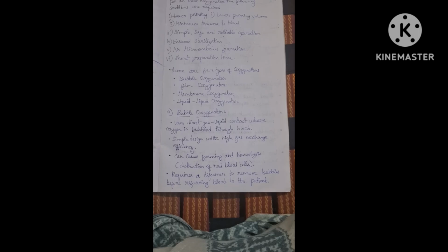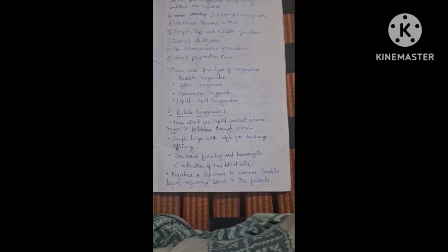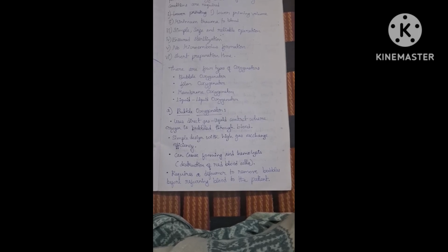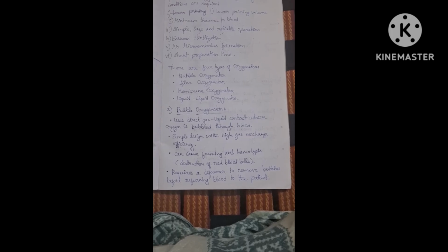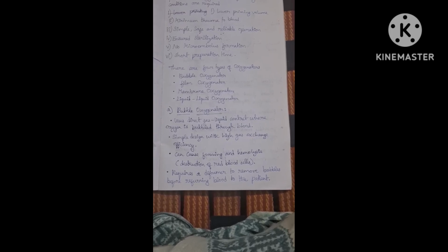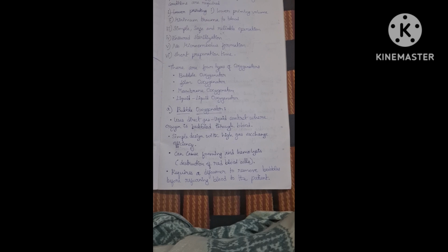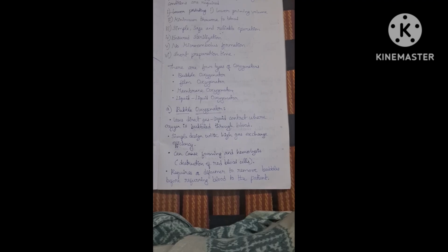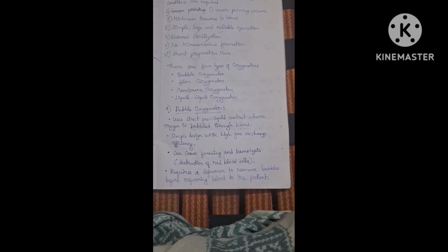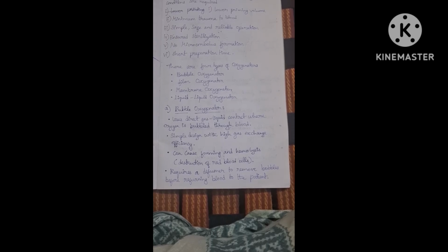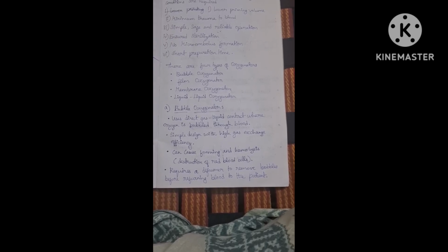The first one, bubble oxygenator, uses direct gas liquid contact where oxygen is bubbled through blood. Simple design with high gas exchange efficiency, can cause foaming and hemolysis, destruction of red blood cells, requires a defoamer to remove bubbles before returning blood to the patient.